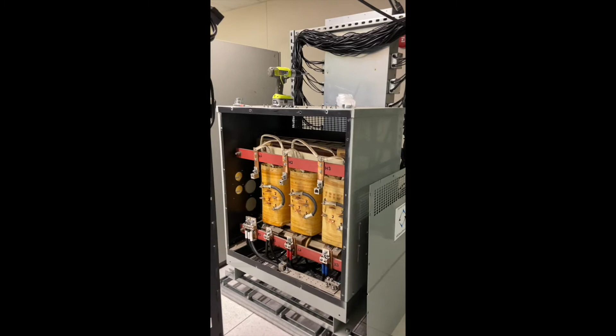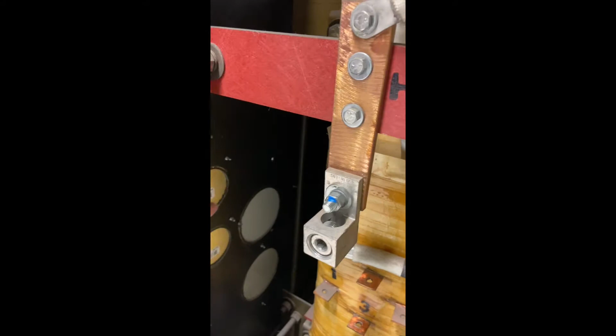The primaries are up top, where you're running the 480 volts in, and then you'll see the secondary voltage there as well. You can also see the knockouts over on the left. This unit came all put together, so at H1 you have your knockouts — this is where you fit either your armored cable or the actual pipes coming out. And then here, this should be a 225 kVA transformer.